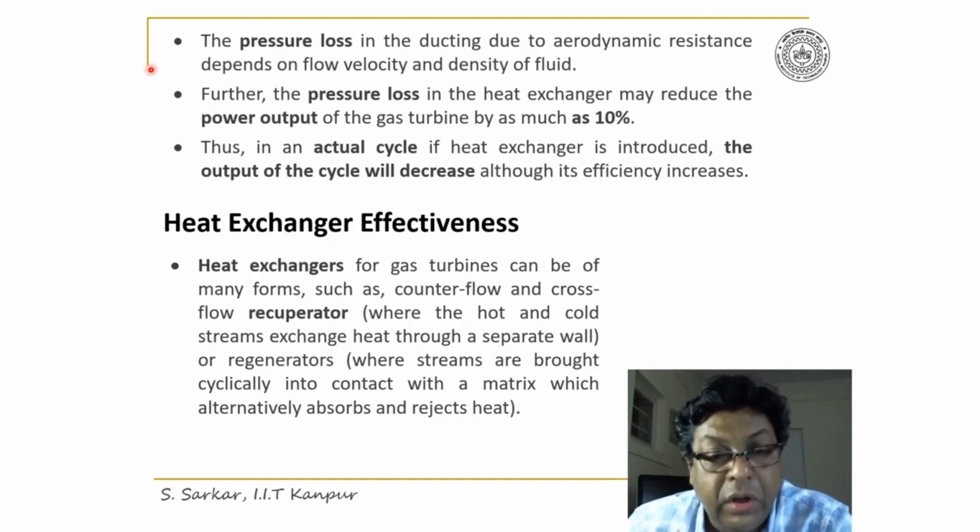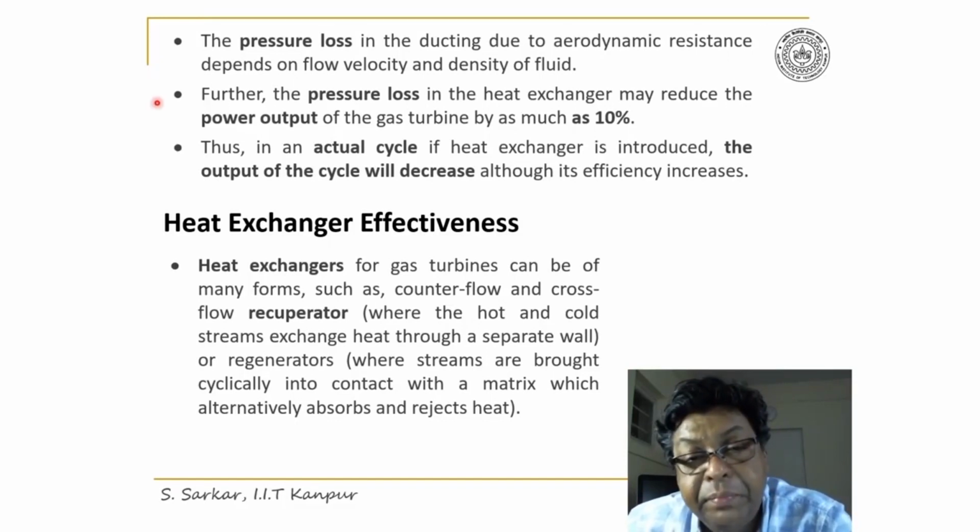It should be noted also that the pressure loss in the heat exchanger may reduce the power output of a gas turbine engine by as much as 10%.